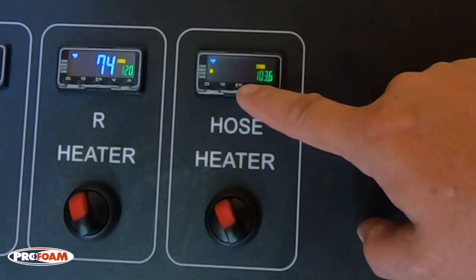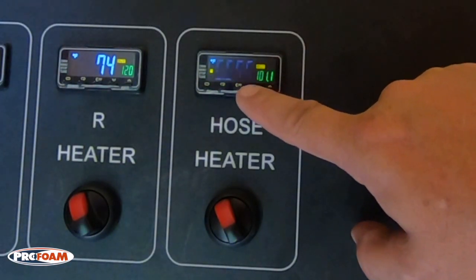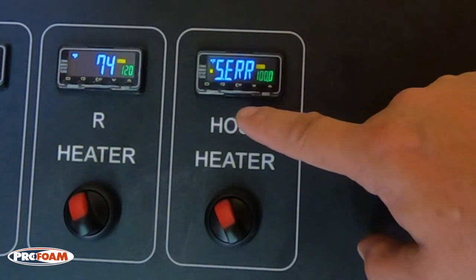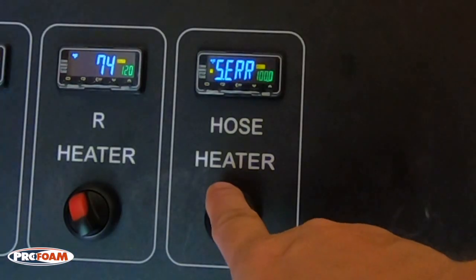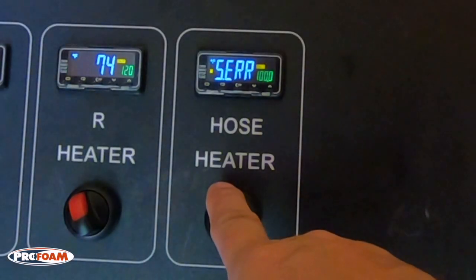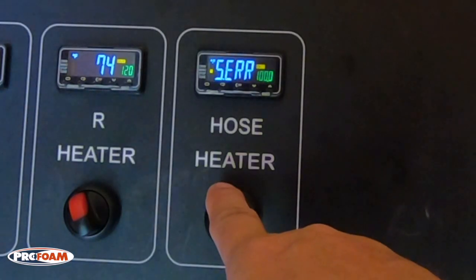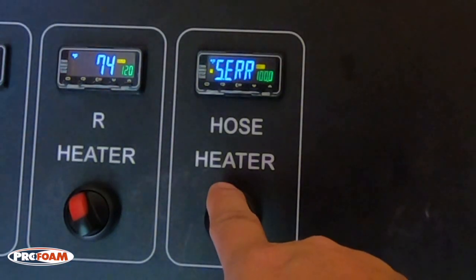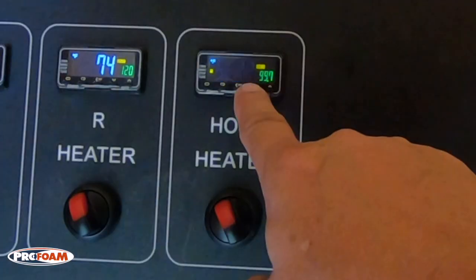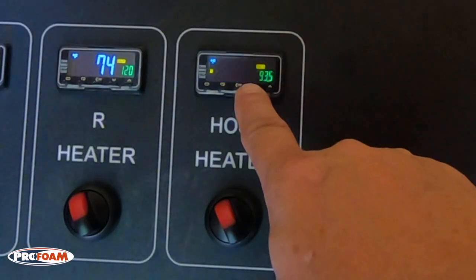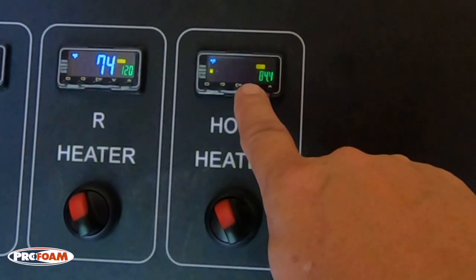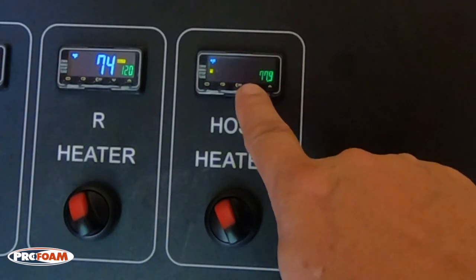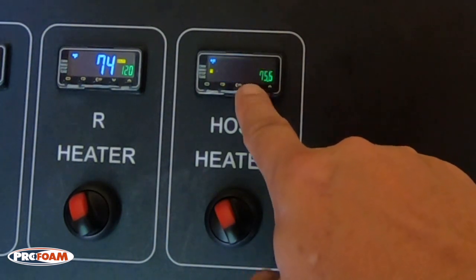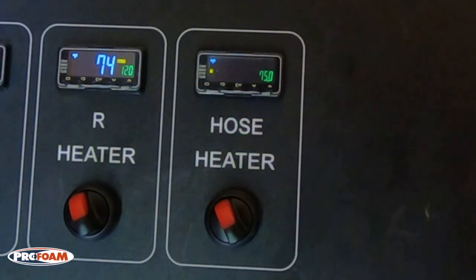Yeah, we'll go a little past, about 105%, but we'll set it at 100.0. Okay, then I can turn my hose heat on, and I would do that maybe for 15 minutes. If you leave it on an excessively long period of time, you could do damage to the hose because it's feeding power out there long past its set point, because it doesn't know what the set point is at this point. So do it for about 15 minutes, and then back this down to about 70-75%. There, 75%, and that's probably going to get you pretty close.